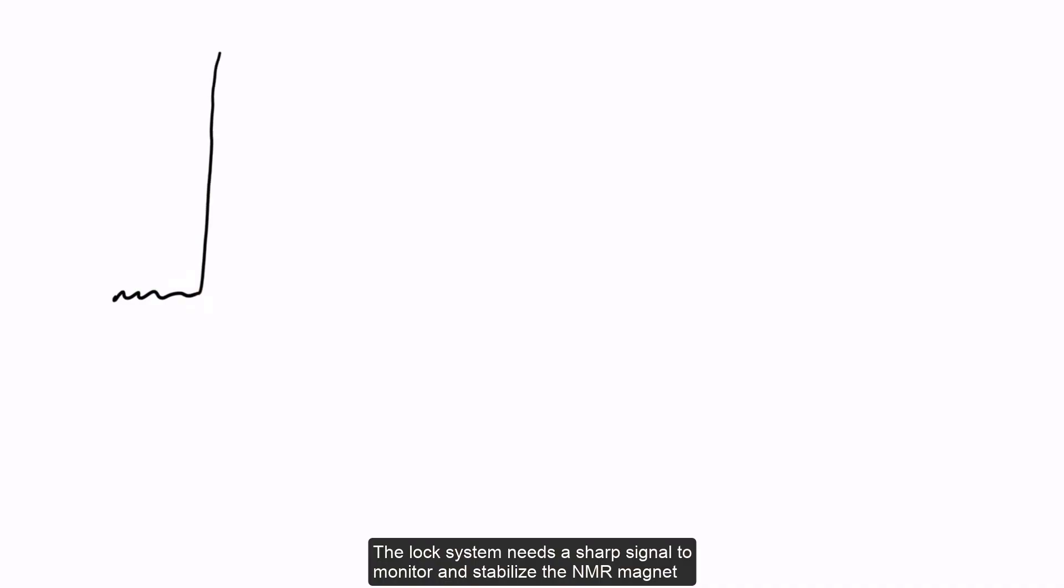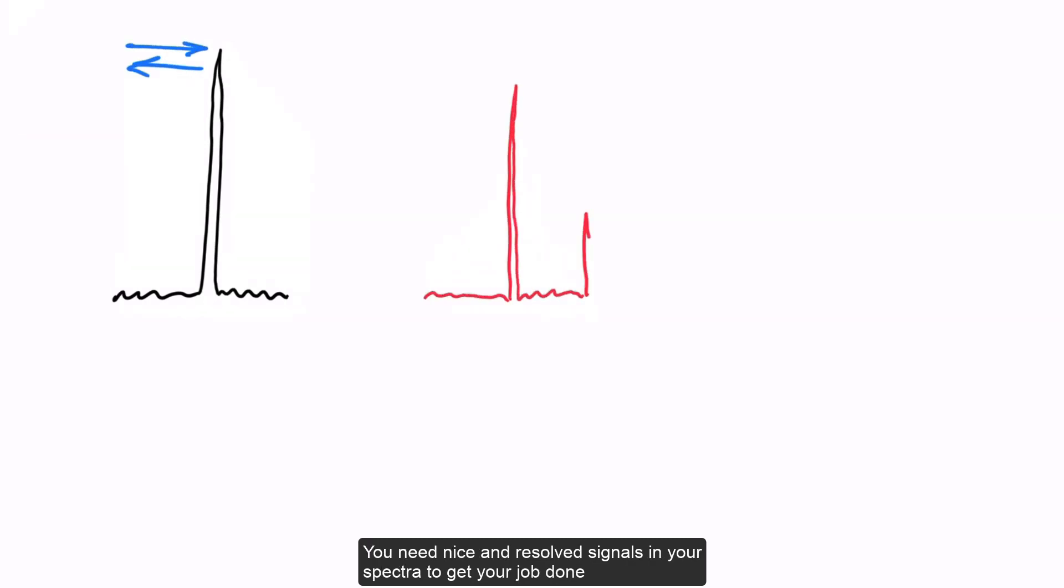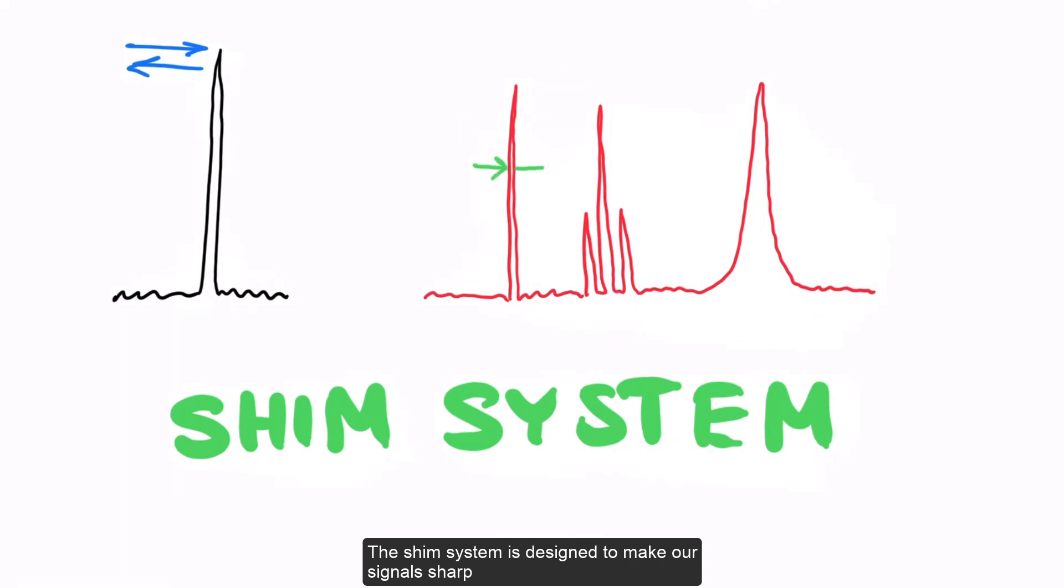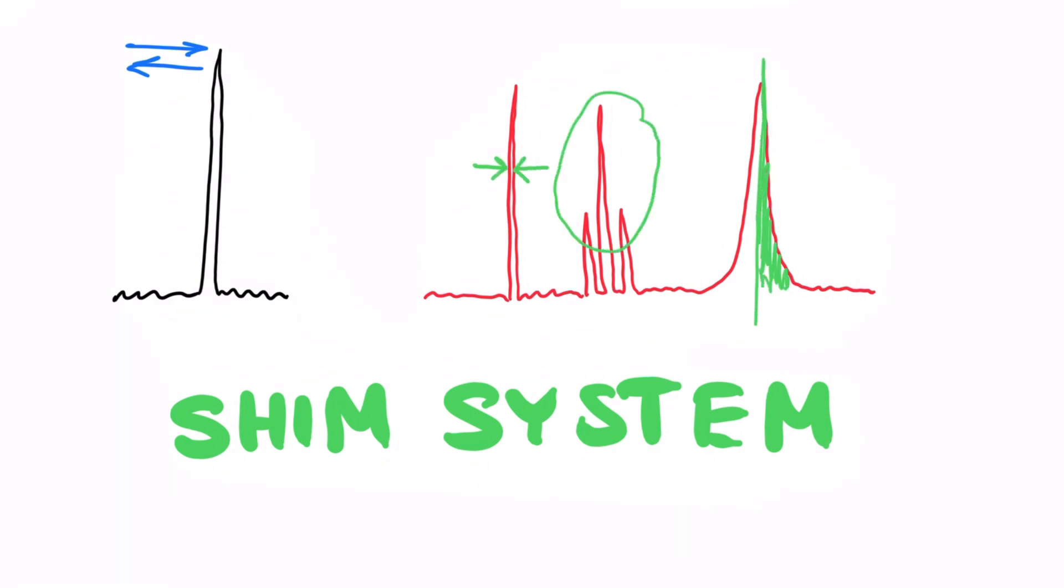The lock system needs a sharp signal to monitor and stabilize the magnet. You need nice and resolved signals in your spectra to get your job done. The Shim System is designed to make our signal sharp, symmetrical and well resolved. Let's discuss how it achieves that.